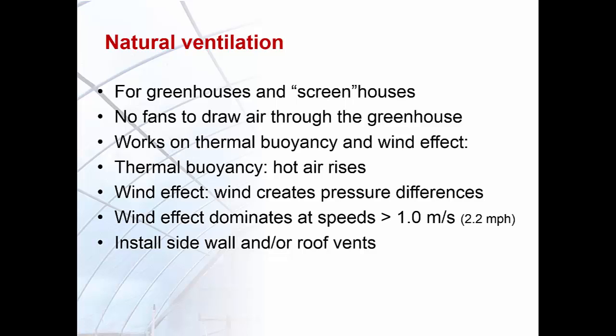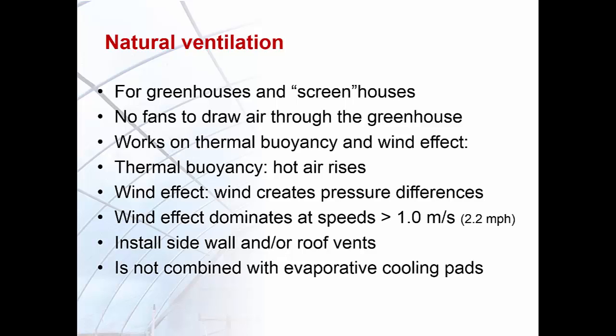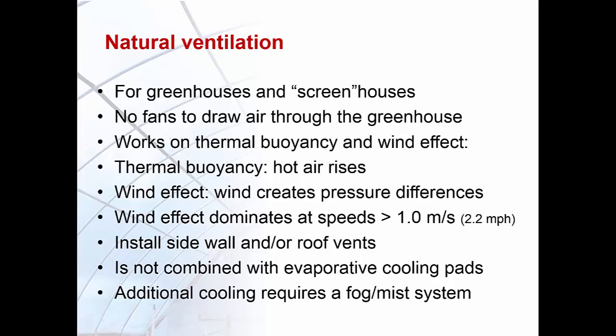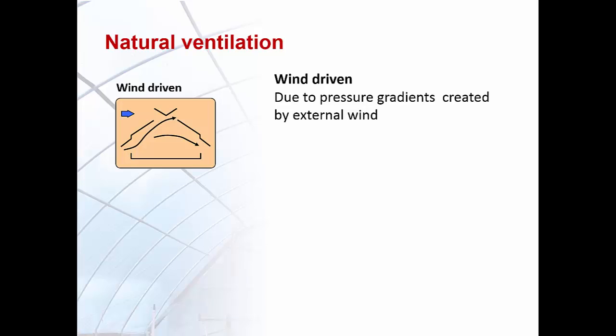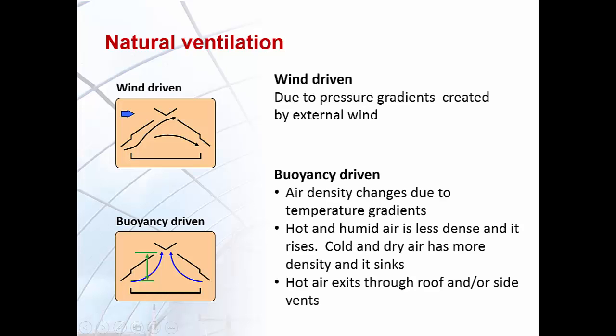Growers need to install sidewall and/or roof vents to achieve proper natural ventilation rates. Natural ventilation systems are not combined with evaporative cooling pads; if additional cooling is required, a fogging or misting system must be installed. There are two types of natural ventilation: wind-driven ventilation due to pressure gradients created by external wind, and buoyancy-driven ventilation, sometimes called the chimney effect.